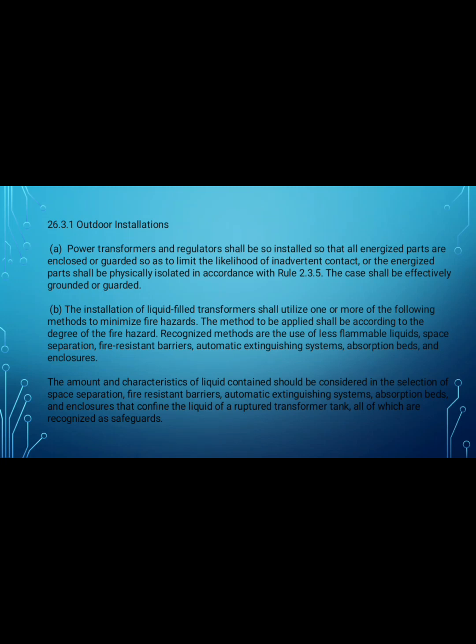2.6.3.1 Outdoor installation. A. Power transformers and regulators shall be installed so that all energized parts are enclosed or guarded so as to limit the likelihood of inadvertent contact, or the energized parts shall be physically isolated in accordance with Rule 2.3.5. The case shall be effectively grounded or guarded.